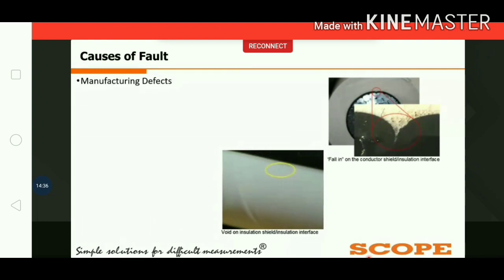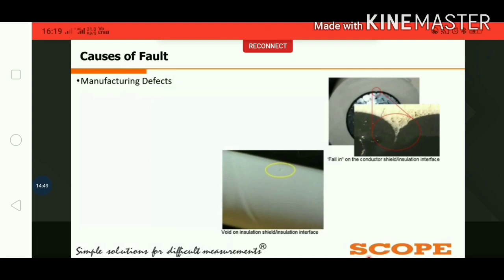During manufacturing, if some contaminants or moisture remain in the cable, over time they slowly develop water trees and electrical trees inside the cable. These slowly developing defects result in degradation of the cable insulation, which is one of the major causes of cable failure.